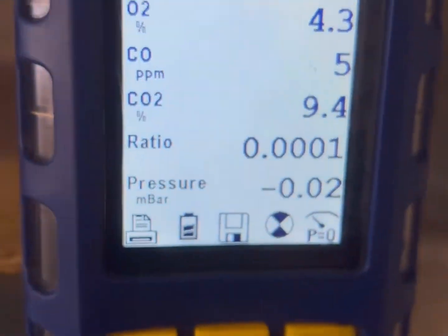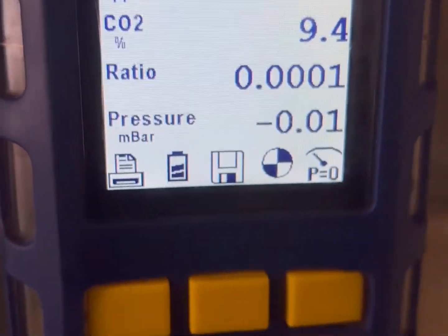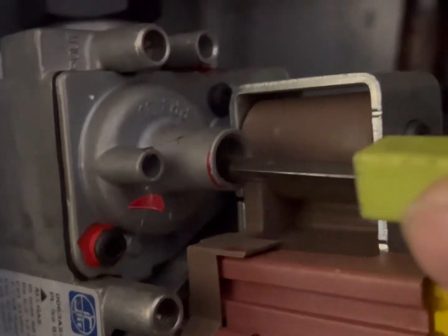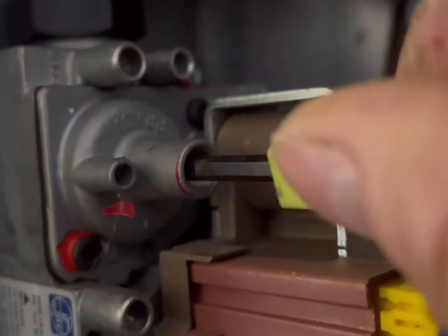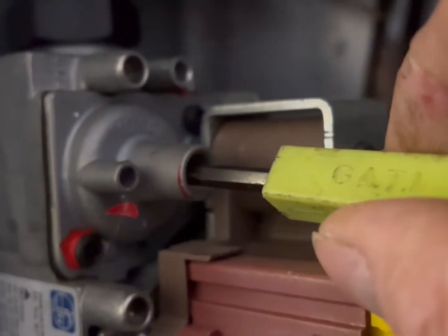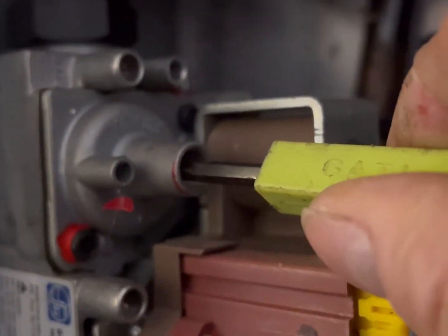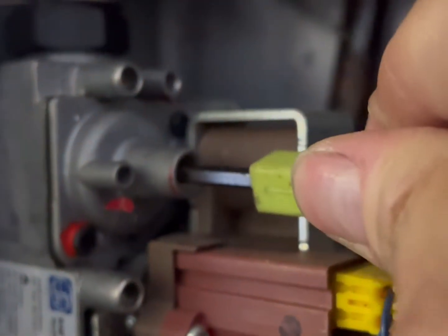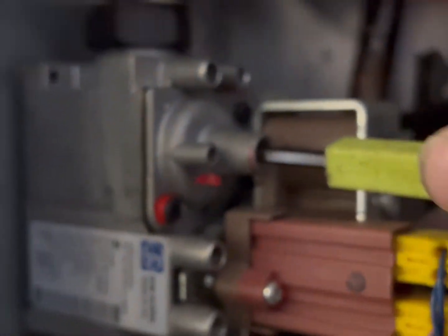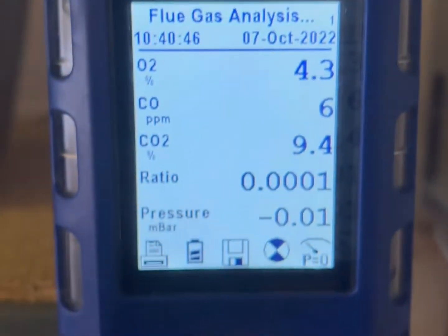At the minute we've got 9.4, which is good really to be fair, but we could adjust that just a tiny bit more — get it down a little lower — because it's meant to be 9.2. So we can come in here on the minimum rate, and we want to go to the right just a tiny bit.